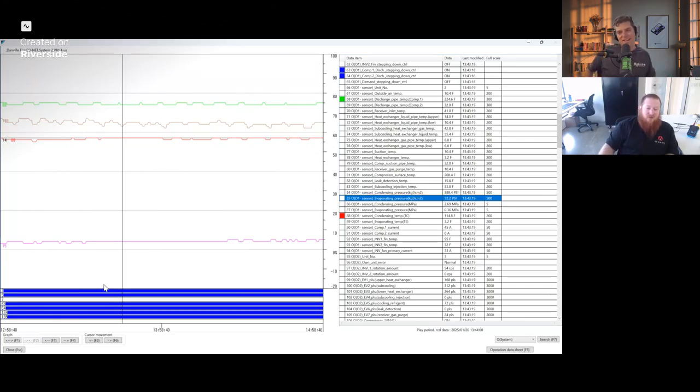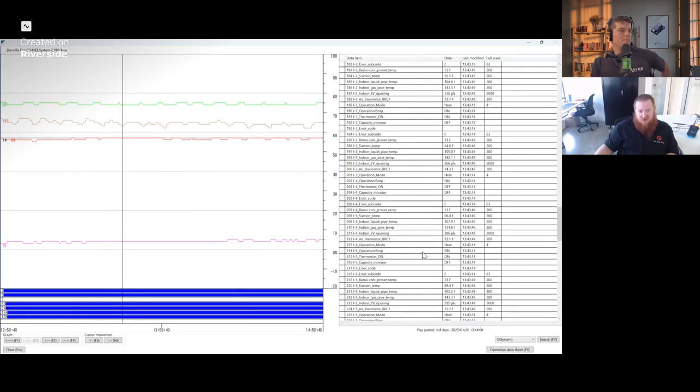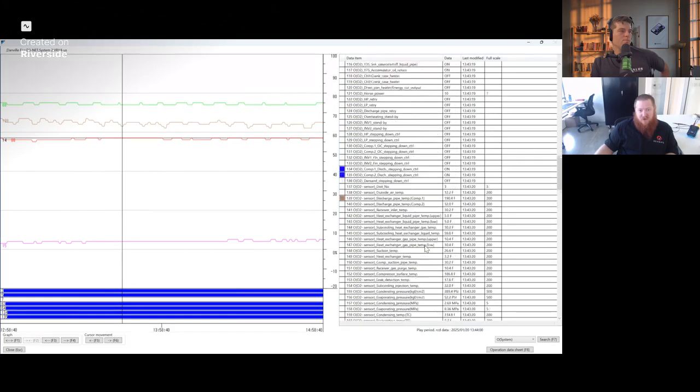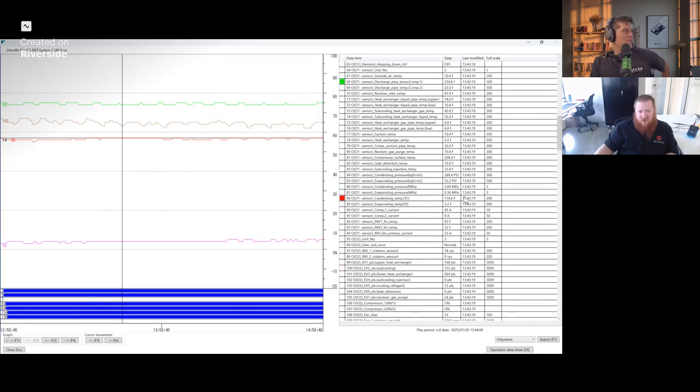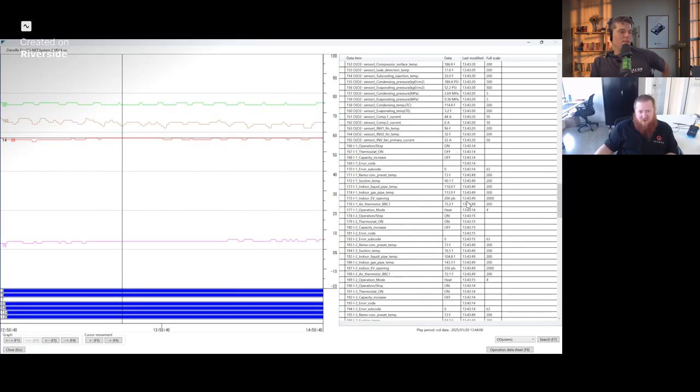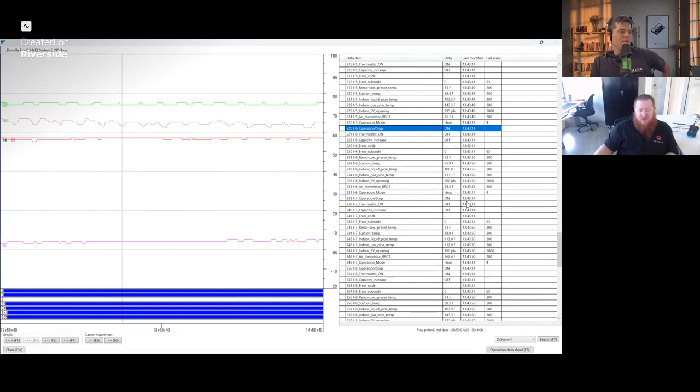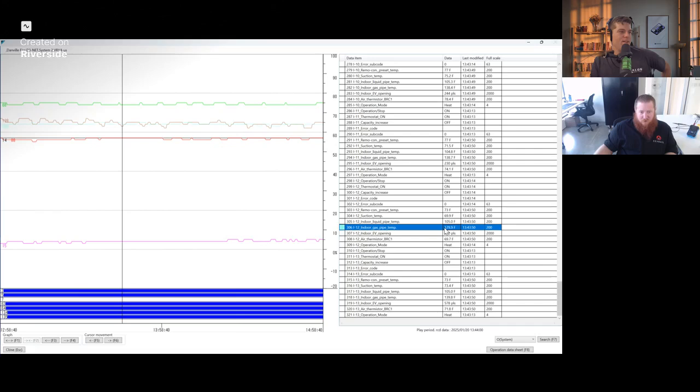So I think a good point of that too is go back to the indoor section and look at the temperatures. Look at the discharge temperature of the compressor versus the supposed gas temperature on the indoor coils, right? So we're thinking we've got 224, 225 degree discharge temperature off that compressor.